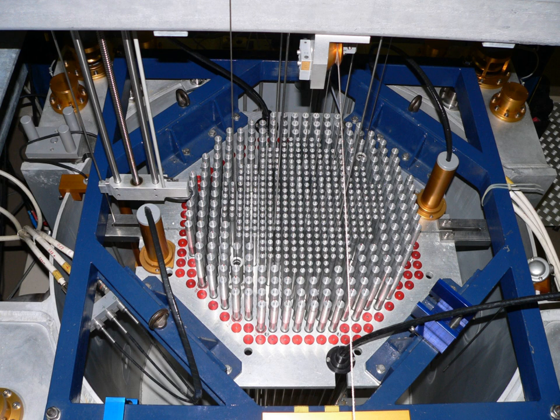At the end of the operating cycle, the fuel in some of the assemblies is spent, and is discharged and replaced with new fuel assemblies, although in practice it is the buildup of reaction poisons in nuclear fuel that determines the lifetime of nuclear fuel in a reactor. Long before all possible fission has taken place, the buildup of long-lived neutron-absorbing fission byproducts impedes the chain reaction.